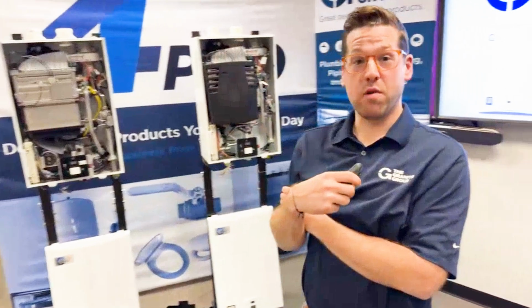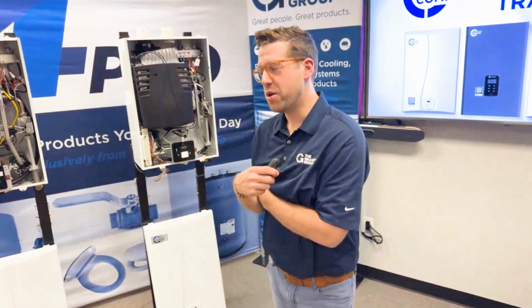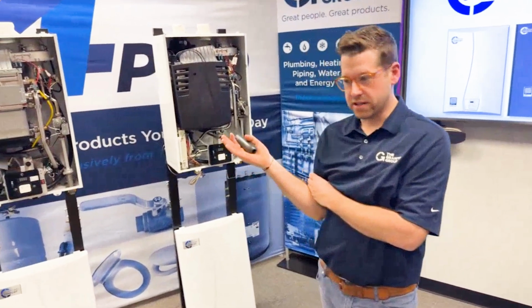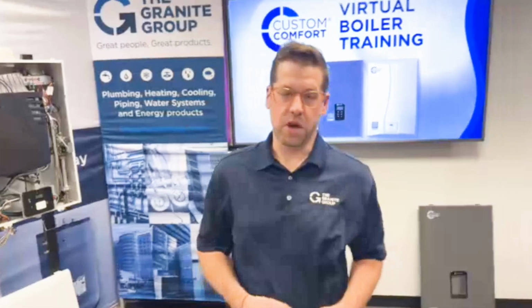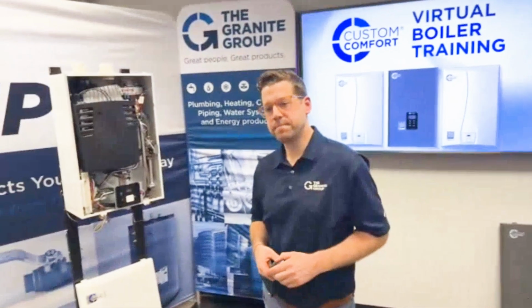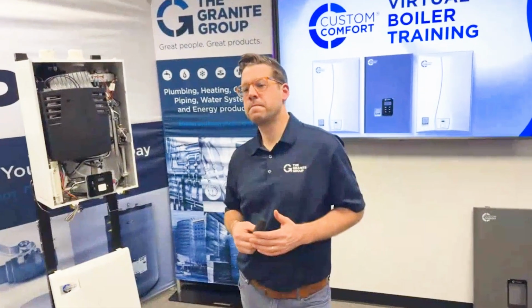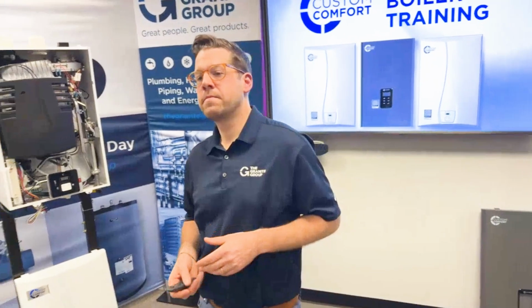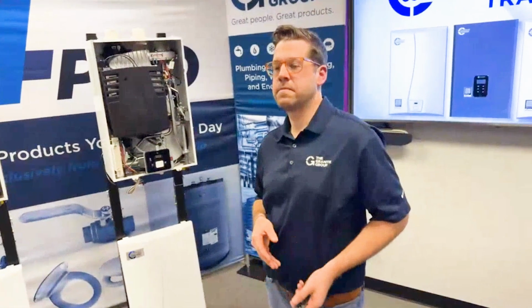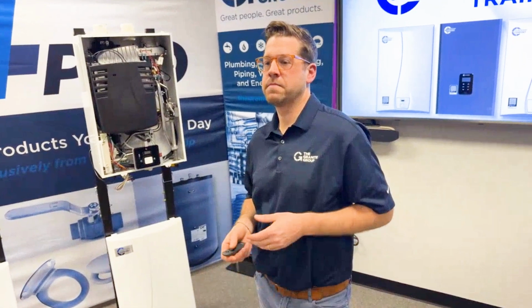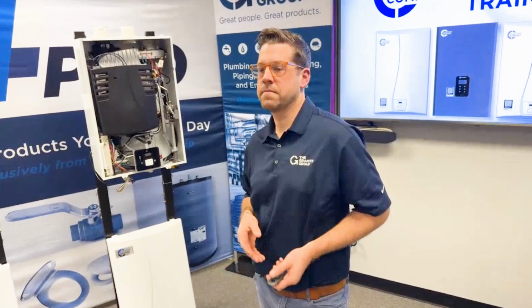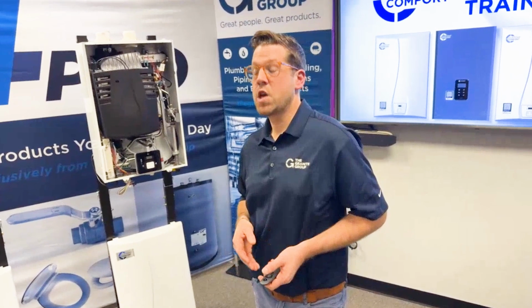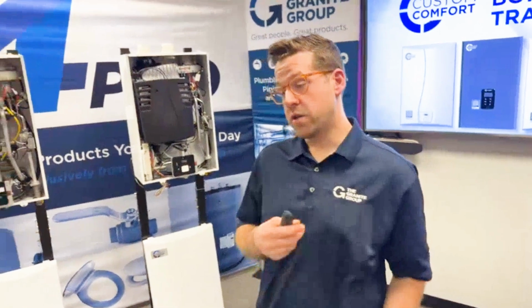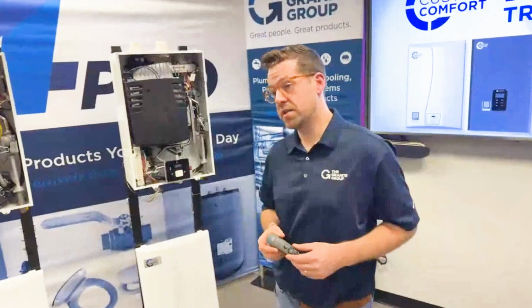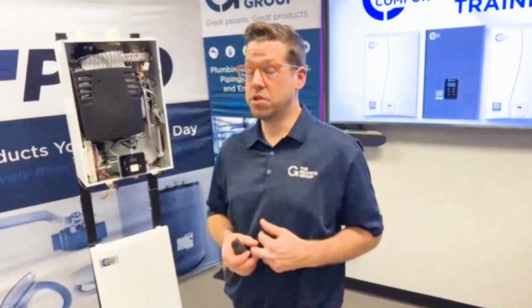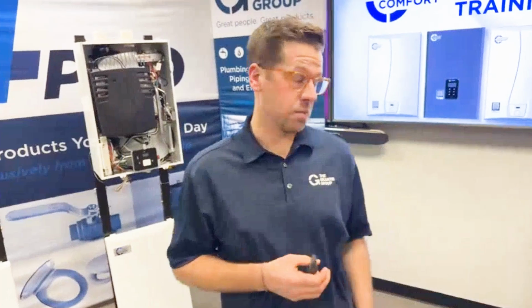We have those available by 4Pro. So yes, they do require a condensate neutralizer, likely a condensate pump. And again, we have those all available under the 4Pro brand. And I believe this one was already answered, but is an external control needed for the domestic return pump? For domestic recirculation? Yes. So the question was, do you need an external domestic recirculation pump? You do need an external domestic recirculation pump.